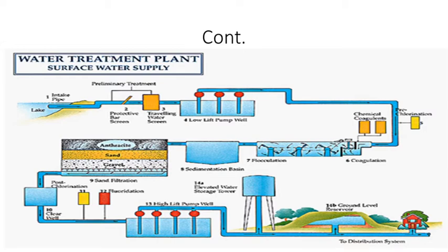And the opposite, if you are thinking about the rapid sand filter, the cost of installation is low because it is a small and compact filter, so it requires less material and less space. Similarly, the cost of operation and maintenance for the rapid sand filter is high. Why? Because the rate of filtration is very high, so we require regular cleaning of that filter. Also, we require replacing the material of that filter, and that increases the cost of operation and maintenance of the rapid sand filter.